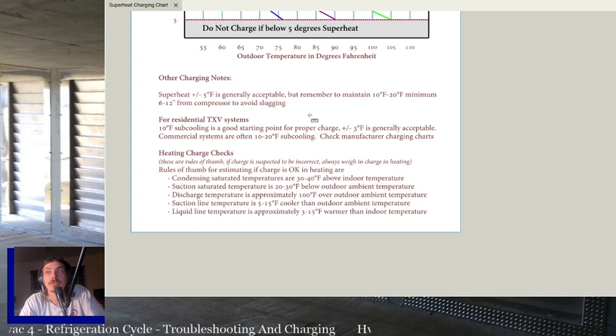Suction saturated temperature should be 20 to 30 degrees below outdoor ambient temperature. Again, if we're talking about trying to pick up heat outside, we can't pick up heat unless the refrigerant is below the outdoor temperature. So you need about 20 to 30 degrees there to try and get that heat from that 30 degree air outside. So if it's 30 degrees outside, your suction saturated temperature of the refrigerant should be probably about 0 to 10 degrees Fahrenheit. If it's not, then you're not going to be able to pick up any heat. It's not going to do what it needs to do.